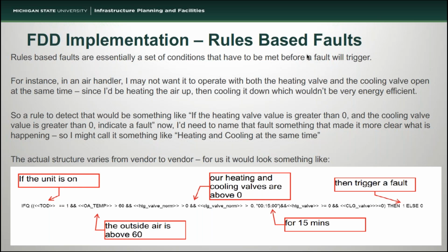I actually have an example here of actual fault logic that we've built. If you look, it starts with an if, and then there is a TOD, which means time of day, is the unit on. If the outside air is above 60 degrees, and we have our heating valve open, and we have our cooling valve open for at least 15 minutes, then trigger a fault, because that is not an operation that we want to normally have happen. Slide.